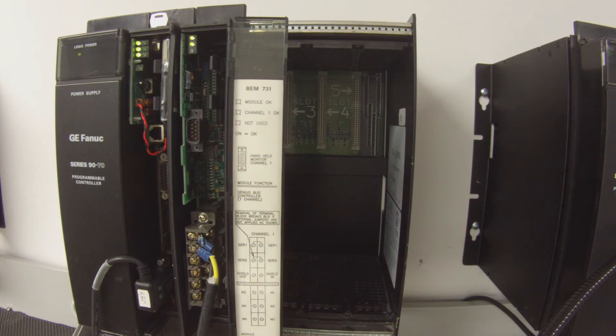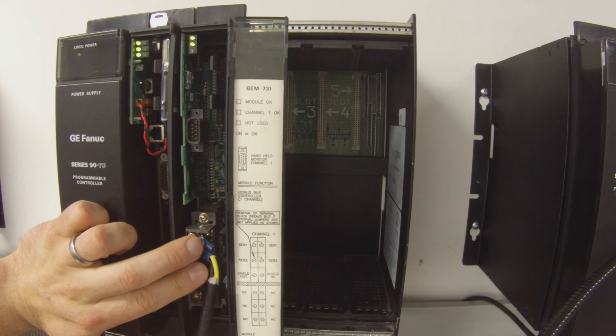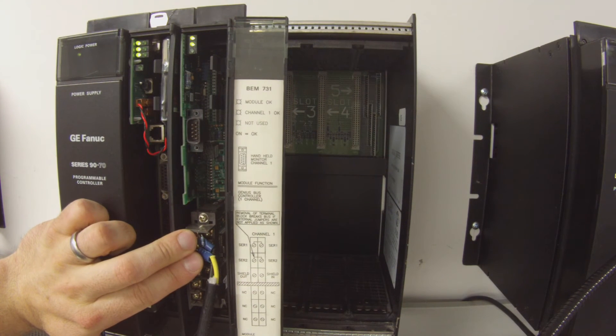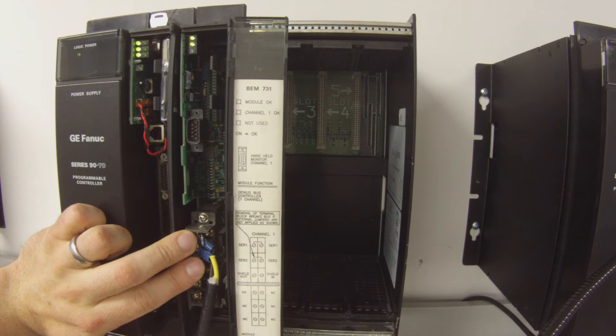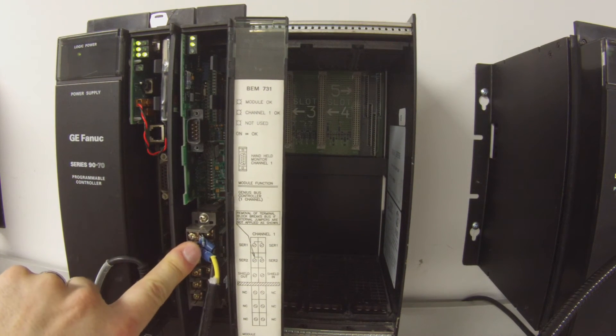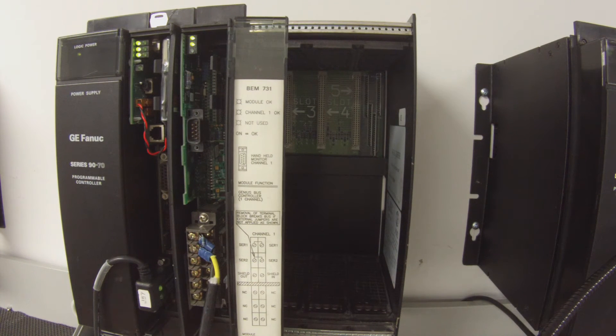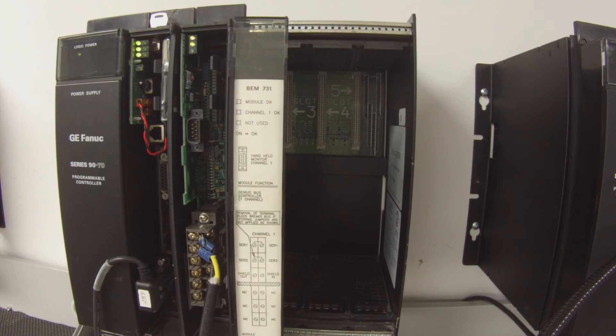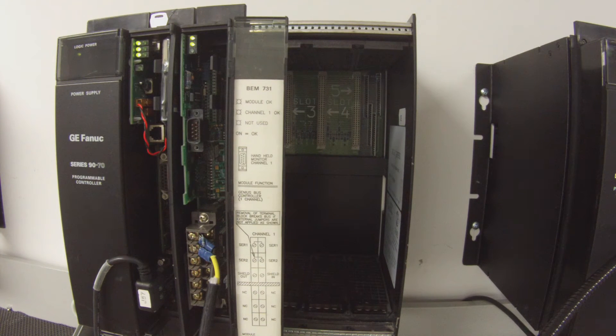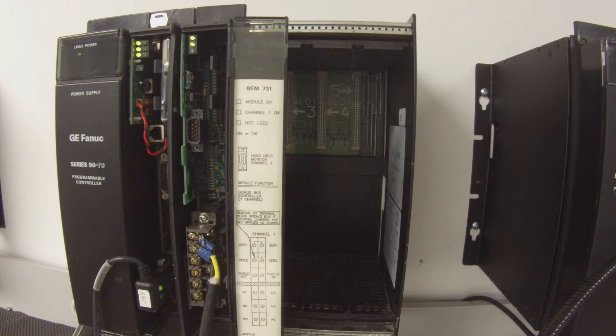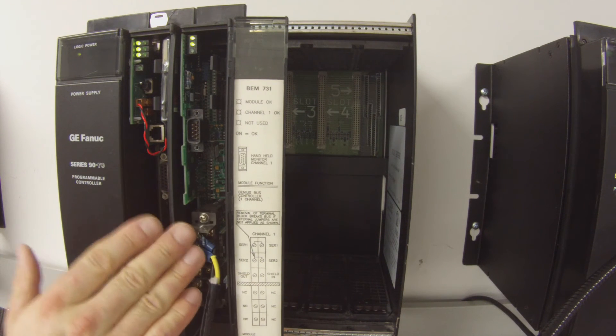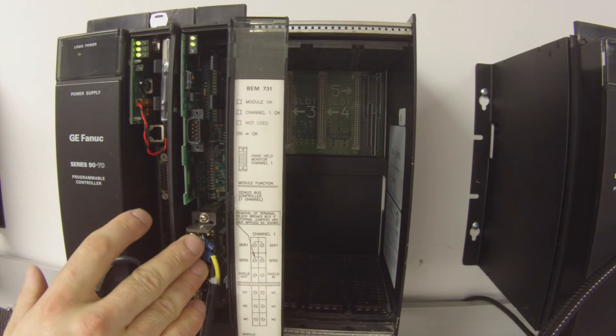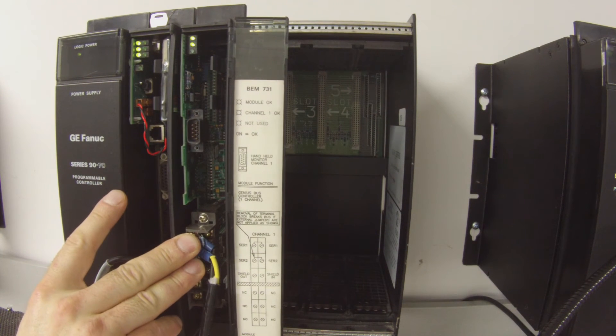There's two things we're going to test. We want to test the address, this serial connection going to a remote block. And as I said before, I have a BBR 101 plugged in. This serial exit is going to the serial 1 and 2 from 1 and 2 on the controller to 1 and 2 on the Genius block device. And what I want to do, you can't see, but I've chosen the block, which is serial bus address or SBA 1, to be the same as what I've configured in Proficy Machine Edition for this, which is SBA 1. And I've also configured it to be a BBR 101.